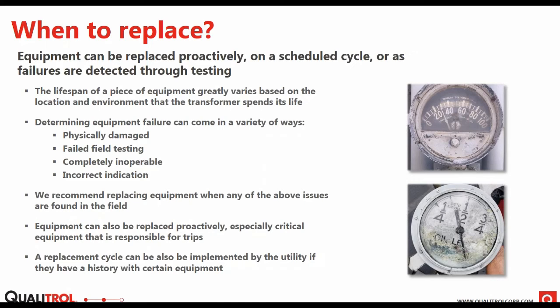So determining equipment failure can come through testing, which we just went through, or a physically damaged unit that is completely inoperable. Say you go up to a temperature gauge and it's just buried at 0 degrees, and you know that the transformer is above 0 degrees. That's a good failure indication. And if you do the ice bath test on a thermometer and it doesn't zero out, you can consider that an incorrect indication.